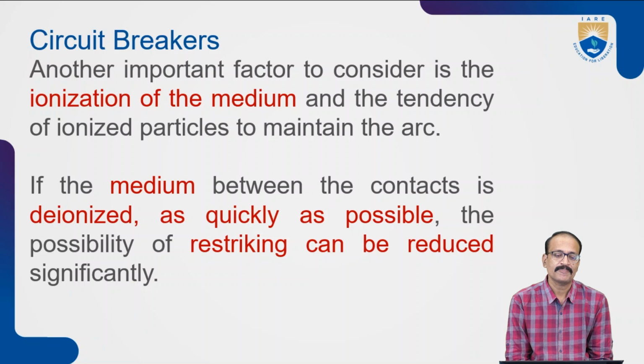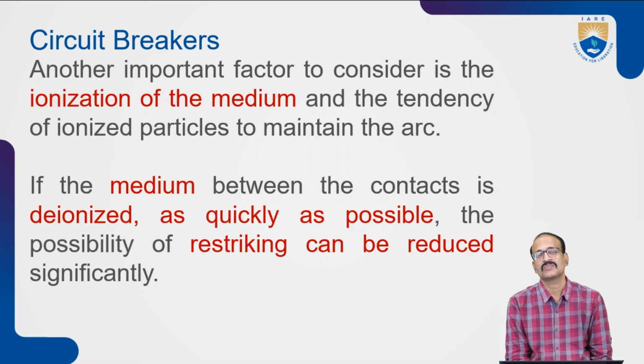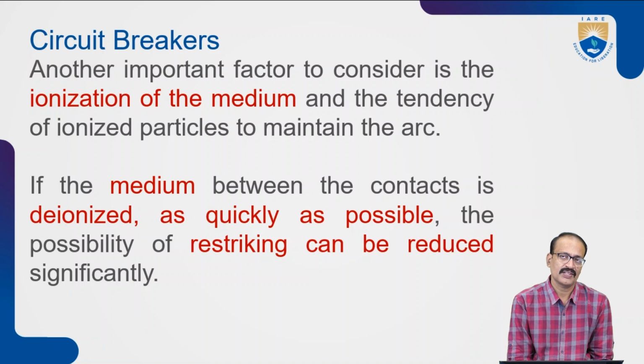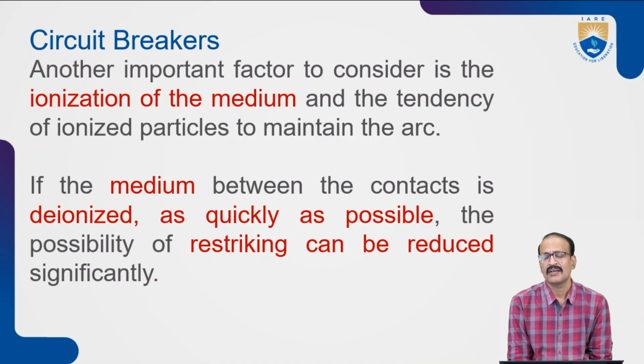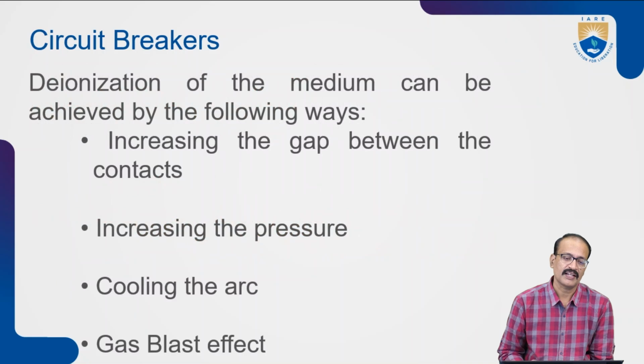And another thing is, we have to consider the ionization of the medium and the tendency of ionized particles to maintain the arc. So if the medium between the contacts is deionized, the main things are potential difference and ionization of the medium. So for ionization we are providing the high resistance and low resistance methods. Ionization means the medium between the contacts, which we have to deionize. Ionization is the main reason here, so we have to deionize as quickly as possible. Then the possibility of restriking can be reduced significantly.